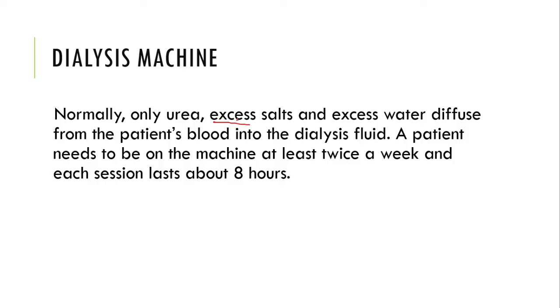If the water in the blood is more than the water in the dialysis fluid, water from the blood will go into the dialysis fluid. Okay, so as long as it's excess, it will be excreted. Are you following? That's why they're saying normally only urea, excess salts, and excess water diffuse from the patient's blood into the dialysis fluid. A patient needs to be on the machine at least twice a week, and each session lasts about 8 hours. Wow, that's expensive if you ask me.